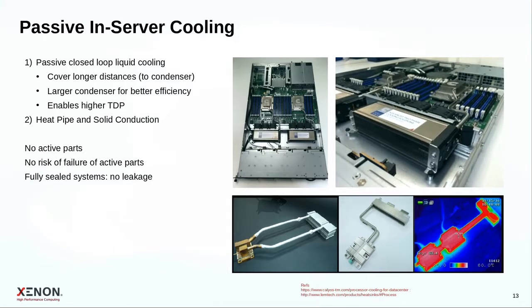Of course, we can also look at passive cooling solutions. The advantage of that, and we've looked into that a little bit as well, is that we can avoid active parts. We don't have any pumps in there which can fail, and we can cover longer distances, and we can have very large condensers for efficiency.